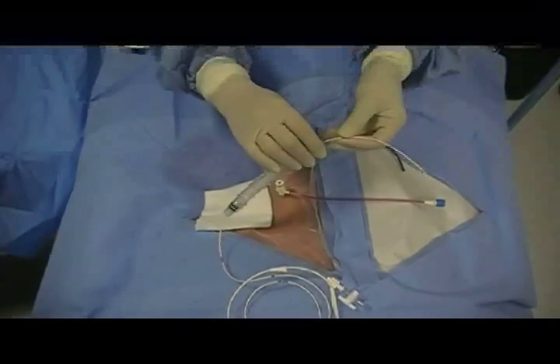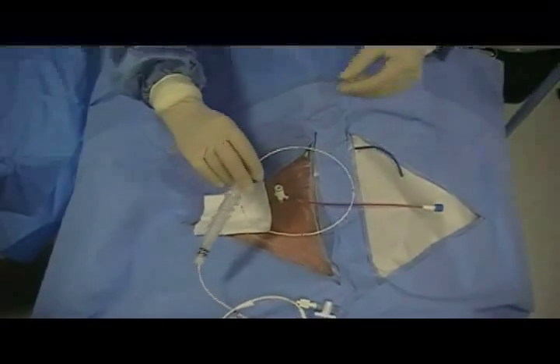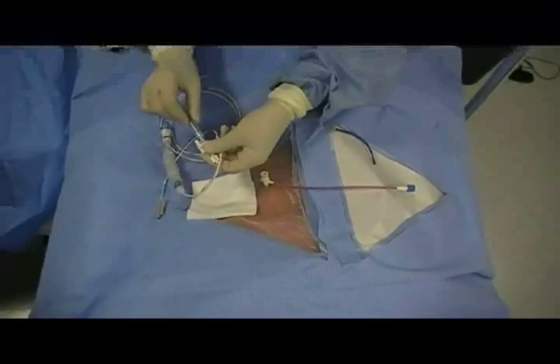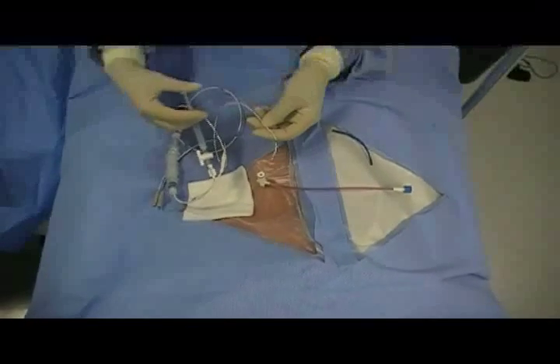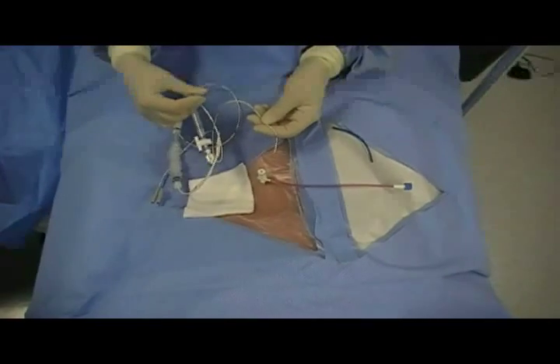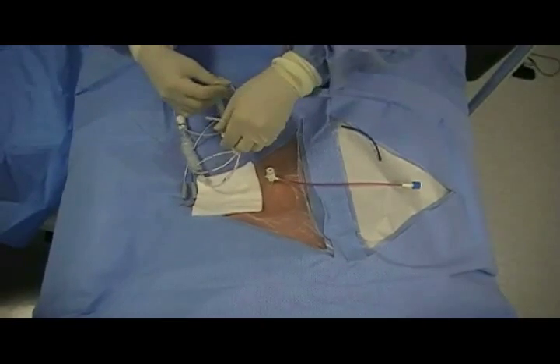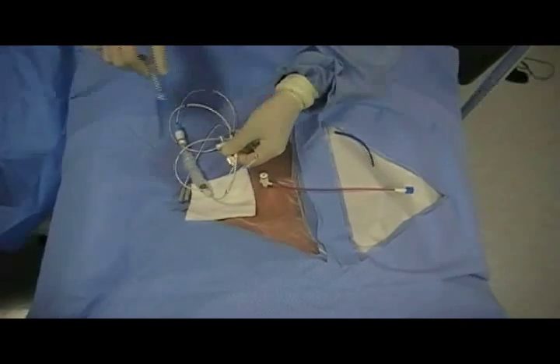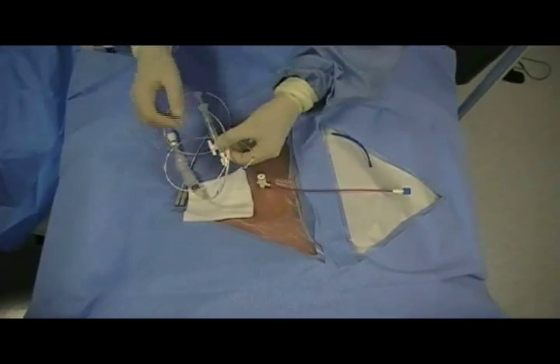The contamination shield should be left compressed until capture is achieved. Next, the balloon is tested at the distal tip of the catheter to ensure that it inflates properly — this usually requires approximately 1.5 cc's of air. Once proper functioning of the balloon is verified, the balloon should then be deflated.